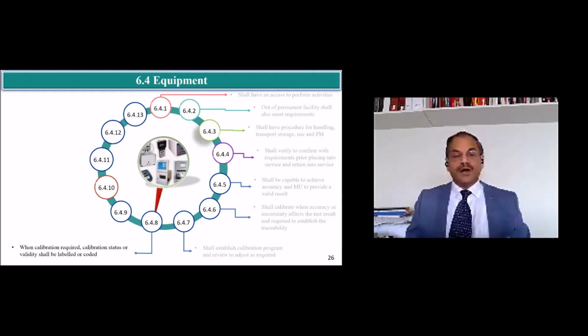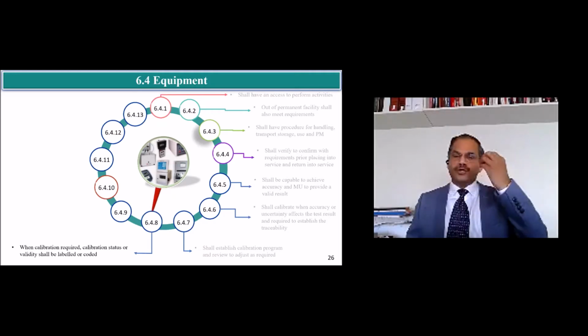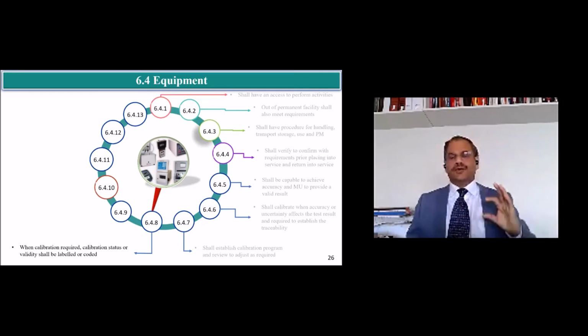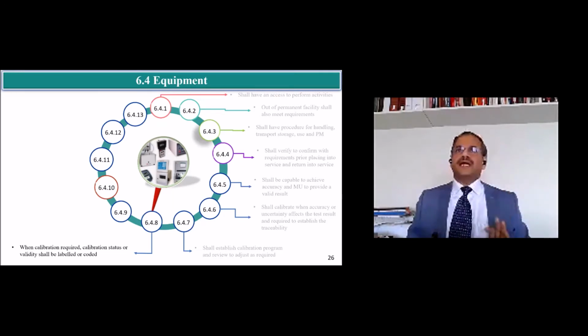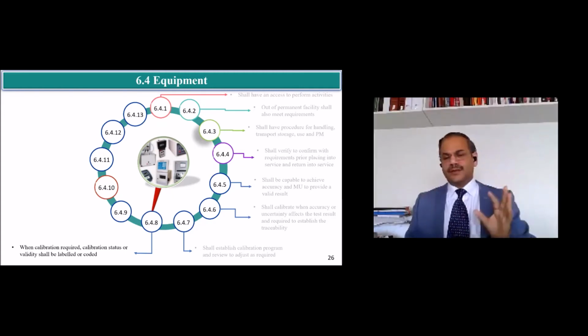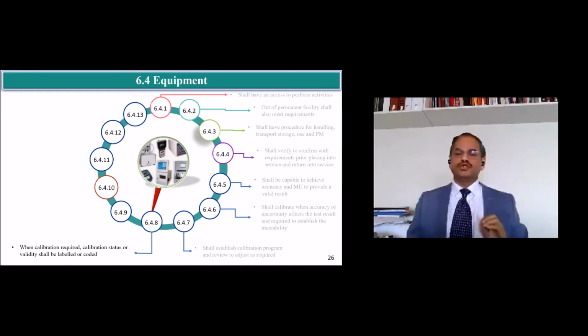Then all the calibration status has to be labeled. How you want to label or indicate it is your own way. But when I go and stand in front of that instrument as a technician in your lab, I should know whether this instrument is valid or not, and whether it is okay to perform the test. Suppose some calibration is expired, I should know as a technician. So you should have some indication by which a technician standing in front of the instrument is aware of the status of the instrument.